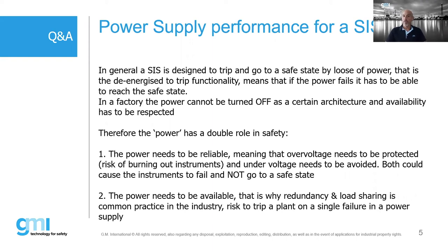So the power needs to be reliable. The overvoltage has to be protected from the risk of burning the instruments, and also the undervoltage needs to be avoided. Of course, it could cause the instrument to fail, not to go to safe state. That is also a risk. Also, the power needs to be available. So that's why the redundancy is very, very important, and in industry has to be applied.